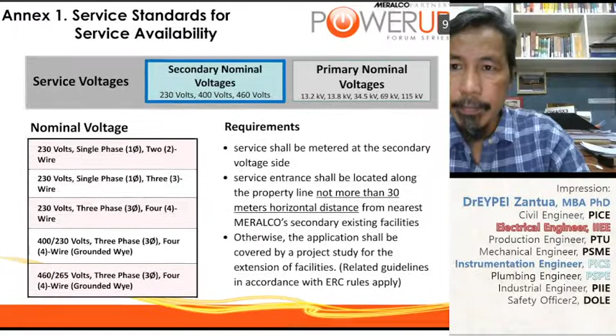Service standards for service availability. Nominal voltages, we know that. We already showed it, talked about it previously. Requirements. Service shall be metered at the secondary voltage side. Okay? Metering. Number 2, service entrance shall be located along the property line not more than 30 meters. So this again, a standard requirement of Meralco, 30 meters horizontal distance from the nearest Meralco's secondary existing facility, secondary line, available outgoing wire. Okay? Measurement is horizontal distance. Okay? So 30 meters.